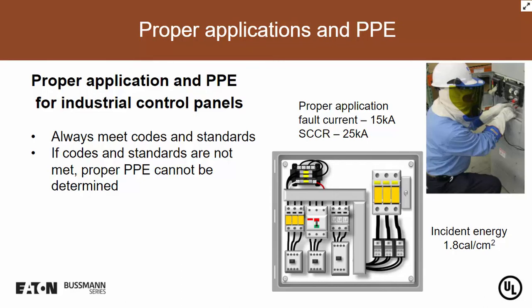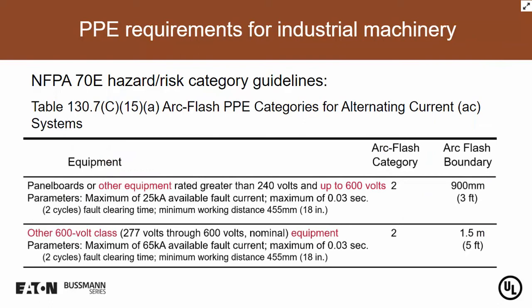The other one I want to get into a little bit is what happens if we didn't calculate it, right? If we didn't calculate it, number one, we've got to make sure that the SCCR is adequate for the available fault current. And once we've determined the available fault current and made sure that the SCCR is adequate, then we can look towards the NFPA 70E chart. So if I'm an OEM and I'm commissioning one of my machines in this building, has the arc flash calculation been completed? In most cases, it has not. So what do you normally wear? Well, sometimes we don't wear anything going to the panel. We're commissioning it, making sure everything's working. Well, that's not exactly correct.